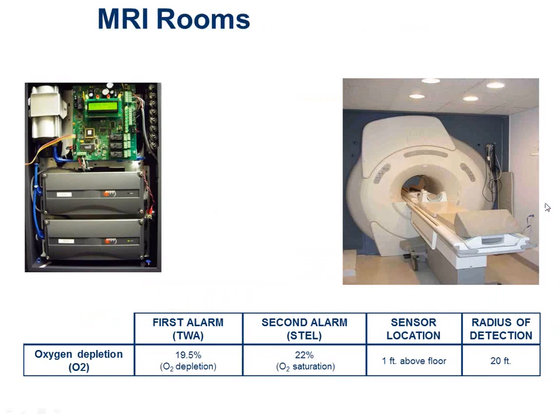Now, one of the things about MRI rooms is they don't want any metal stuff in the room, as you probably are aware. So on these systems, I have to use a sample draw type system, which we're showing you up there on the left-hand side. So if you've ever been in an MRI room, the technician gets you all set up, slides you into the tube, then they go behind the lead wall and run the machine from behind it, because they don't want to be exposed all the time. You're just there one day. They're there every day, every hour. This panel would go back in that same room behind the lead wall. So all the metal components are behind that lead wall.